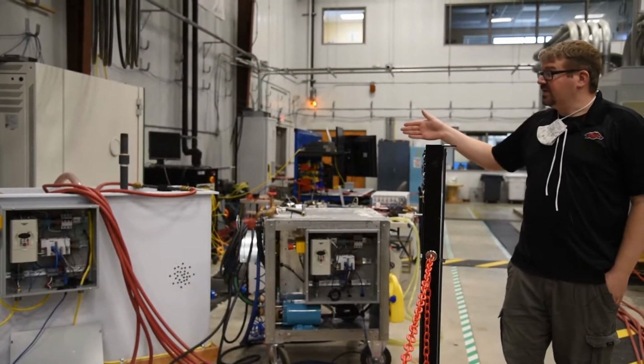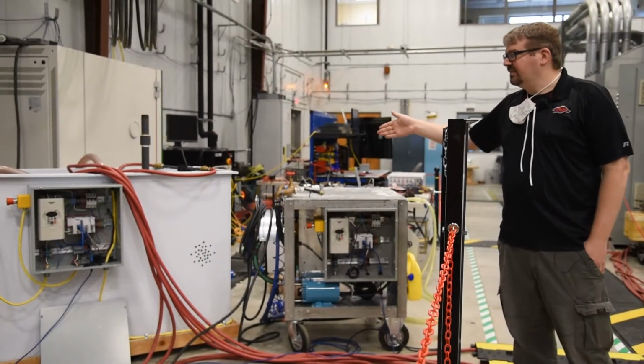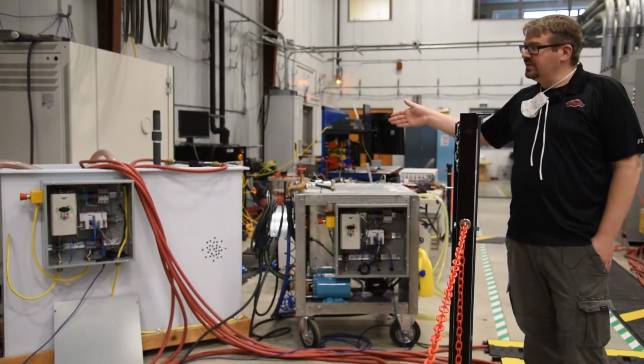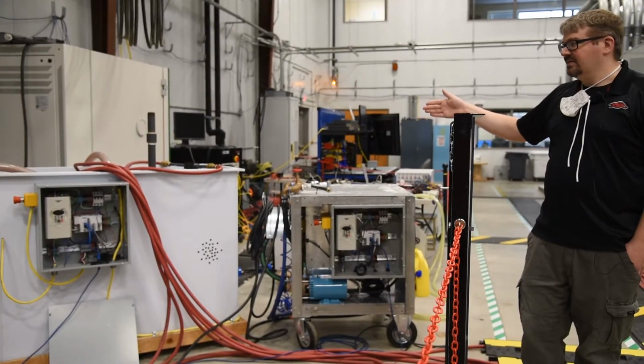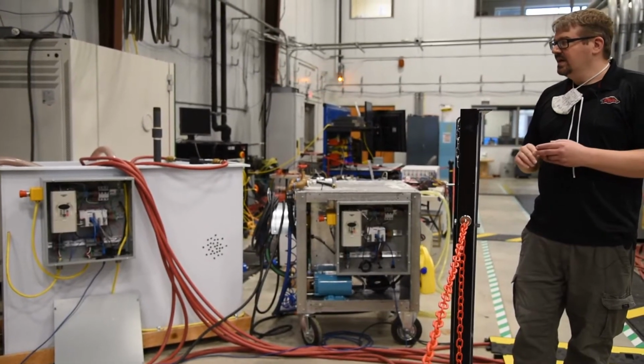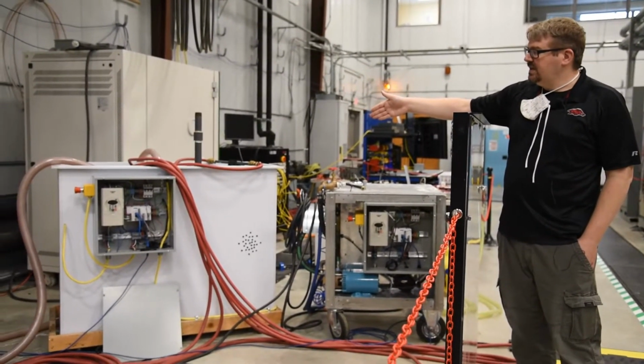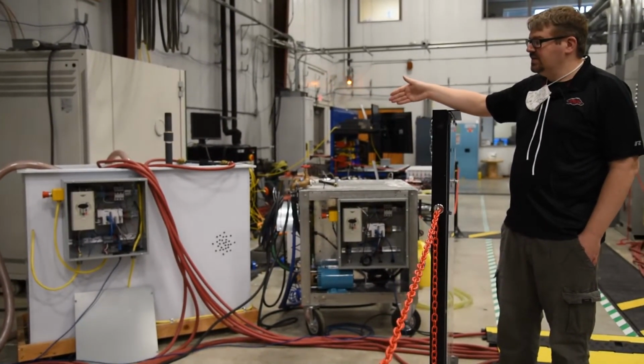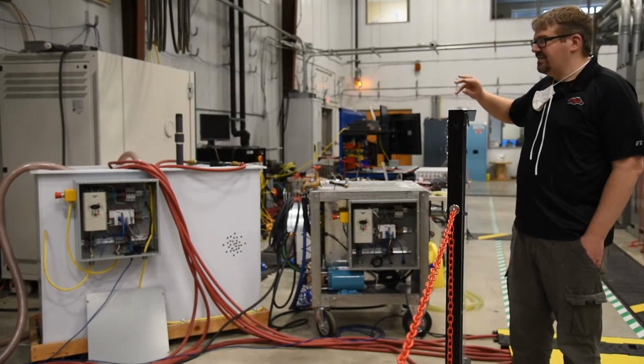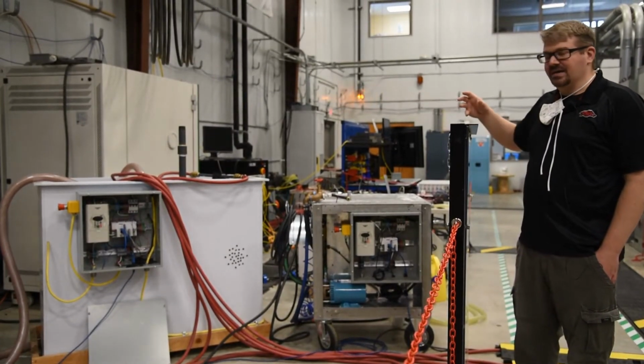So this is just a couple of examples of some of our student projects. These are 2 chillers we have, and previously this heat exchanger would just basically run off of line voltage. You would plug it into the 208 plug, and it would run at whatever line frequency was happening right then. As we're doing more and more testing of silicon carbide inverters for grid connected and transportation applications, we need to know more precisely what the coolant is, and we also want to be able to control the flow rates. So what the students did over the summer was they integrated a PLC that also included some pressure transducers, temperature transducers, and a flow sensor, an ultrasonic flow sensor, as well as a motor drive. And so now, instead of just having to plug this into the wall and getting whatever, we can actually sit there and remotely control all of these devices and collect all the data remotely.